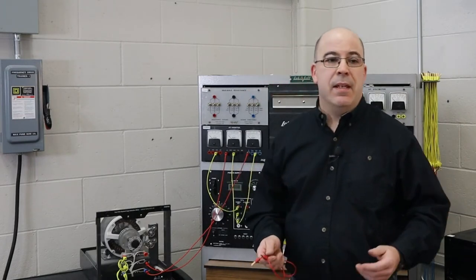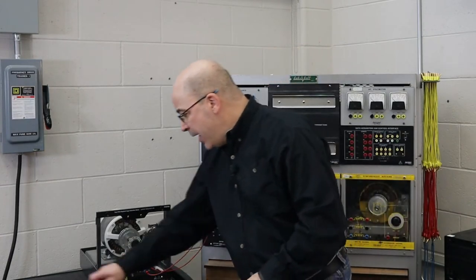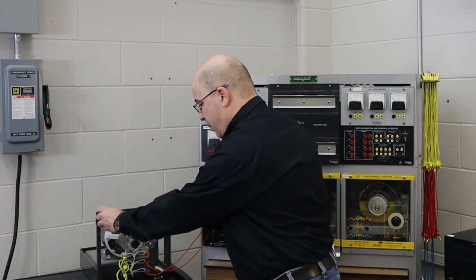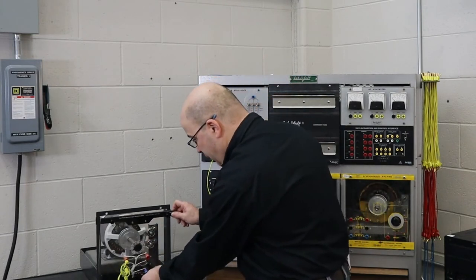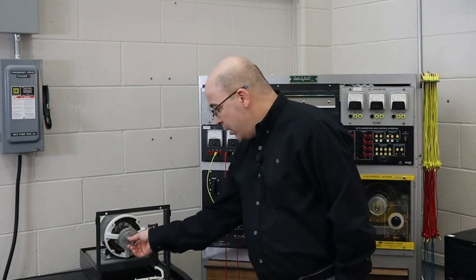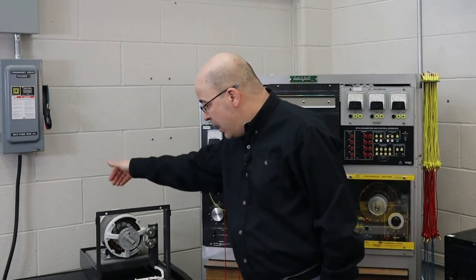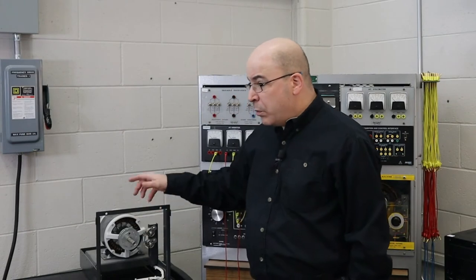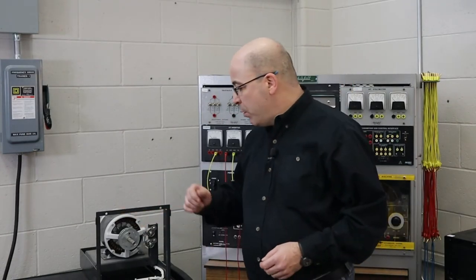Now an interesting note is that electric motors depend on counter EMF. Now what is counter EMF? Well the fact is that when the motor is operating the shaft is turning. When the shaft is turning it's cutting against the magnetic field that is creating the rotation. That creates an induced voltage inside of the rotor bars.